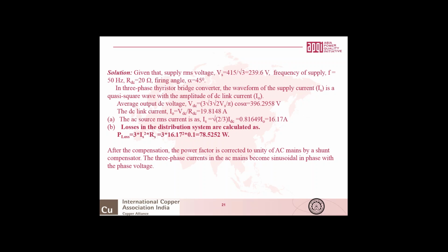Why root 2 by 3? Because out of 180 degree, the current is flowing only for 120 degree. So 120 divided by 180 degree times IDC, and that's the current, 16.17 ampere, the RMS current in the distribution system at the input of this converter. So losses in the distribution system are calculated. Since it is a three-wire system, the loss will be P loss equal to 3 into IS square RS, equal to 3 into 16.17, that's the RMS current we calculated, square, into RS, that's the feeder resistance 0.1 ohm, and this becomes 78.5252 watt.